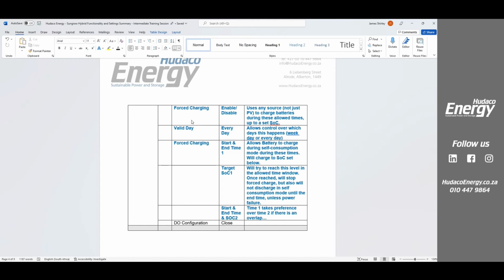But you know that at 4 p.m. maybe the solar power isn't as much. So there we would enable every day my forced charge to start at 1600 to end at 1700, and I want you to charge it to 85% or 80% or 60% or 100%, whatever it is. And you can actually do this twice a day. Okay, remember, this will not only use solar power, it will use solar power and grid to charge. Okay, you don't have to go and reset this every day. You set it once and the system will just do that.